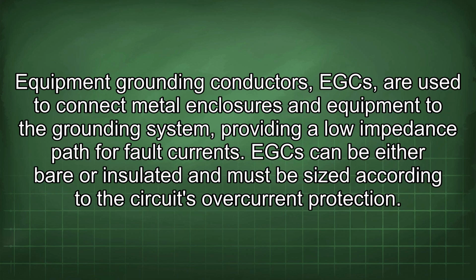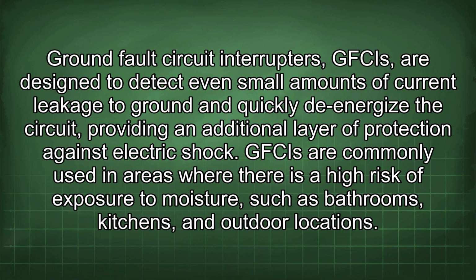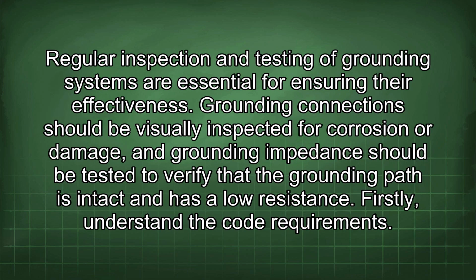This helps to minimize voltage differences and reduce the risk of electric shock. Equipment grounding conductors (EGCs) are used to connect metal enclosures and equipment to the grounding system, providing a low impedance path for fault currents. EGC can be either bare or insulated and must be sized according to the circuit's overcurrent protection. Ground fault circuit interrupters (GFCIs) are designed to detect even small amounts of current leakage to ground and quickly de-energize the circuit, providing an additional layer of protection against electric shock. GFCIs are commonly used in areas where there is a high risk of exposure to moisture, such as bathrooms, kitchens, and outdoor locations. Regular inspection and testing of grounding systems are essential for ensuring their effectiveness. Grounding connections should be visually inspected for corrosion or damage, and grounding impedance should be tested to verify that the grounding path is intact and has a low resistance.